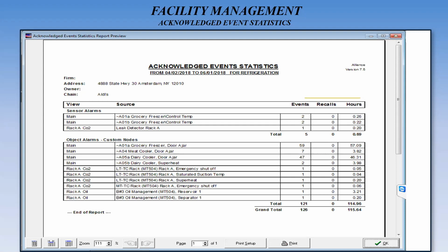So for some product, it might be a half hour before an alarm gets triggered. Other product, it might be an hour. Other product, it might be an hour and a half. So the first trip you have is the alarm itself, whatever you tell us to do: a half hour, 1 hour, 1.5 hours.